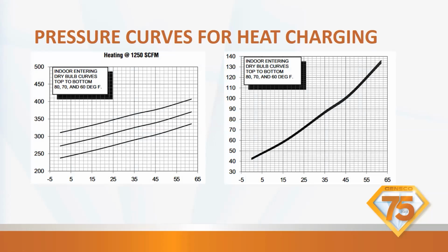These are the pressure curves for heat charging. The one on the left is the high side. The one on the right is the low side. Those diagonal lines in the middle are indoor temperature. The bottom is the outdoor temperature. So you're going to go to the outdoor temperature, say it's 35 degrees outside. We're going to go to the outdoor temperature, and then our indoor is 70 degrees.